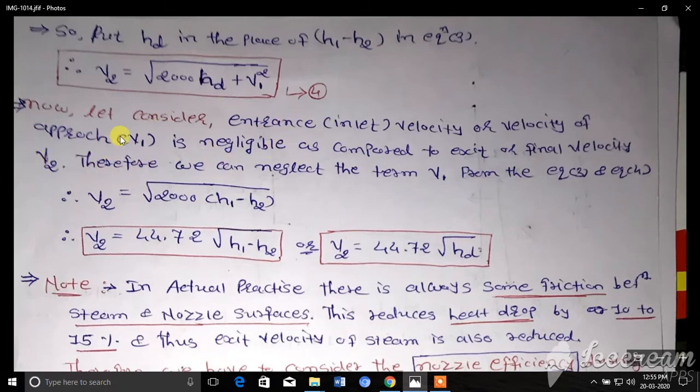So V2 is very much higher than V1, so we can easily neglect this term V1 from equations 3 and 4. These equations can be rewritten as V2 equals square root of 2000 H1 minus H2. The square root of 2000 is 44.72, so we can rewrite this equation as 44.72 times the square root of H1 minus H2, or we can rewrite H1 minus H2 as HD.